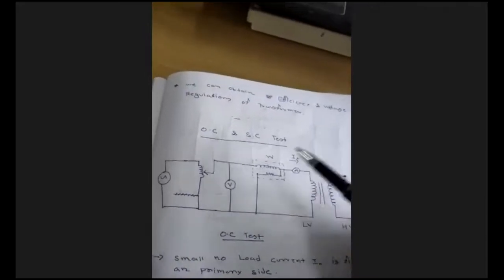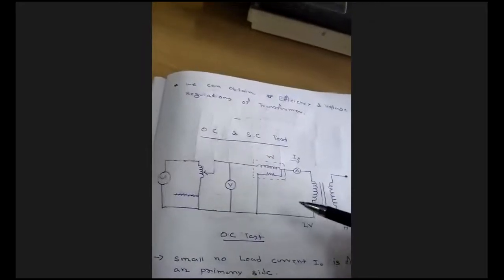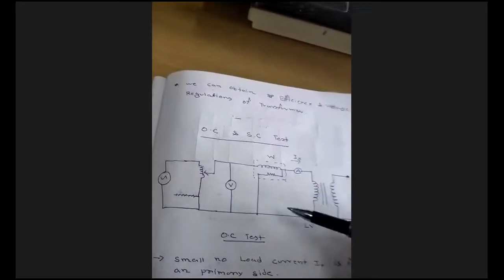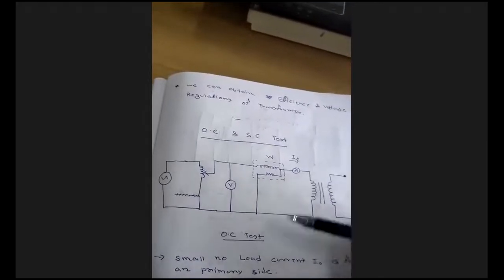एंड एक चीज हमें हमेशा याद रखना कि कोर लॉस depends upon the voltage and copper loss depends upon the current. तो प्राइमरी साइड में क्या हो रहा है, इस प्राइमरी साइड में I square R, ये जो लॉस है, इट इज नेग्लिजिबल because the current is flowing very minimal. Okay, ट्रांसफार्मर में दो लॉस होता है, कोर लॉस एंड द कॉपर लॉस. द कोर लॉस बेसिकली डिपेंड्स अपॉन द वोल्टेज एंड कॉपर लॉस डिपेंड्स अपॉन द current. But on the primary side, when we are conducting the open circuit test, the primary side I square R loss, ठीक है, ये लॉस क्या होगा, ये दैट इज वेरी नेग्लिजिबल.